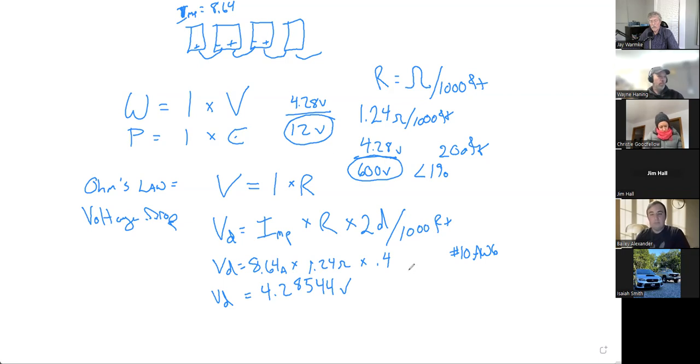In your book, trying to think which page, the resistance characteristics, for some reason 80 something. Right off the bat, it's a thicker wire, so that means it has less resistance, which means it would be more acceptable. Yeah, so on page 84, if I look at 4-aught, then the resistance of that is not going to be 1.24. It's going to be 0.0608.